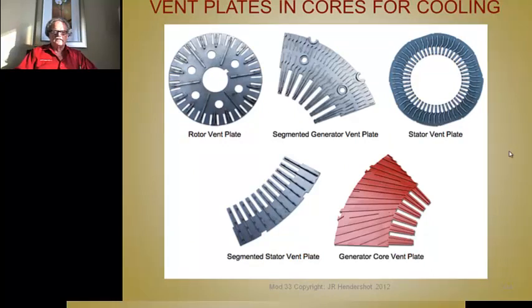In some of the earlier slides, I discussed several times the ventilation plates that are used in cores to provide cooling passages. And here are some nice close-up pictures of some of these. Here's a ventilation plate used on a rotor of a motor, probably an induction machine.